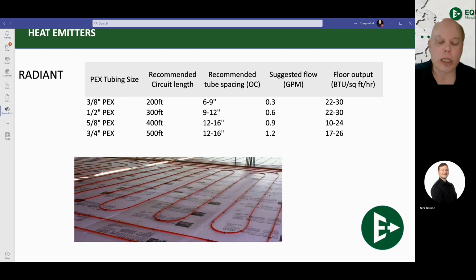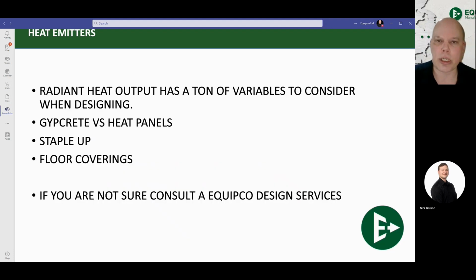Radiant is the only system that truly needs to be designed in order to maximize comfort. It is very susceptible to the installation details that you are putting in with it. So it really should be designed with someone who understands and can calculate the BTUs that are required and then can reverse that into the actual flows required. That can tell us how to balance our manifolds, how to calculate our loop lengths, stuff like that. I'm not saying radiant's bad, not by any means. I'm just saying it is the only system where there are no cut and dry numbers with regards to how many BTUs you're going to be getting out of it.